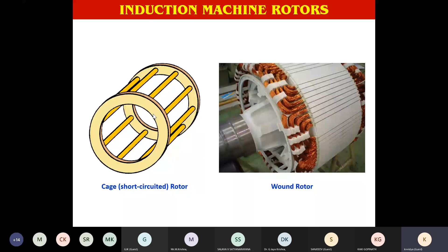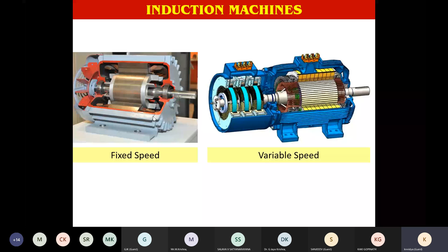Rotors of the generators use 2 technologies. One is the cage rotor, the squirrel cage rotor. Naturally, you cannot control the speed. The second one is the wound rotor. All the fixed speed wind turbines use the cage rotor design, whereas variable speed wind turbines use the wound rotor design. And this is the first or the simplest wind turbine. There is no speed variability or controllability. You just purchase an induction motor. Induction motors will operate only below synchronous speed, because there will be a slip of 1% or 2%. The same machine, if you operate above synchronous speed, will act as a generator.